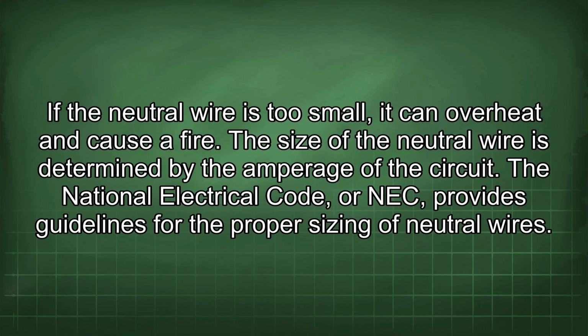If the neutral wire is too small, it can overheat and cause a fire. The size of the neutral wire is determined by the amperage of the circuit. The National Electrical Code, or NEC, provides guidelines for the proper sizing of neutral wires.